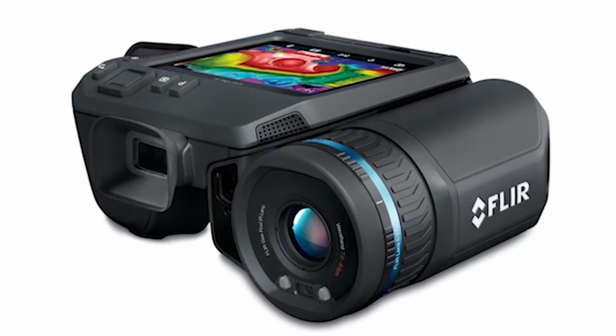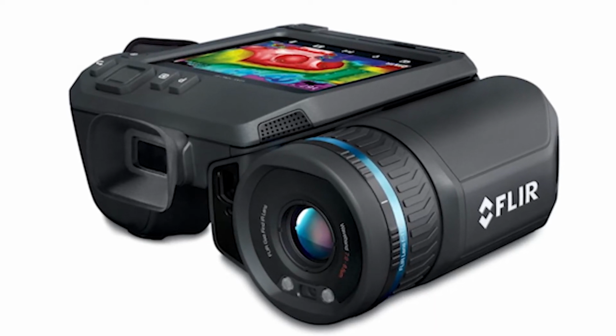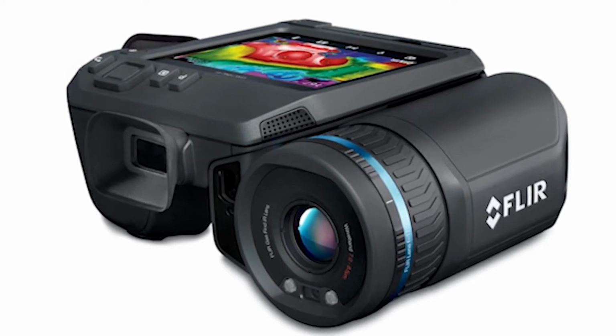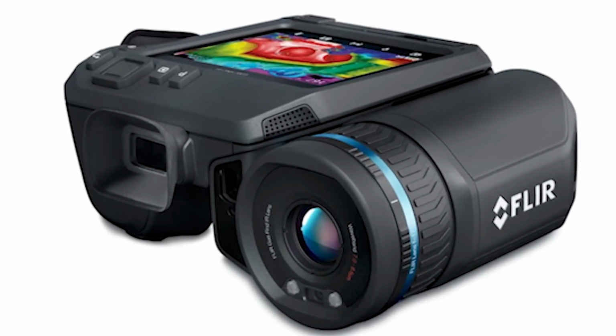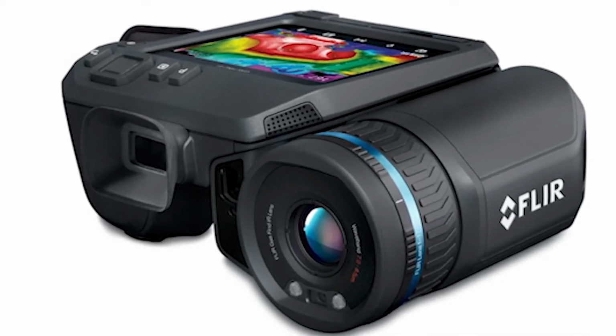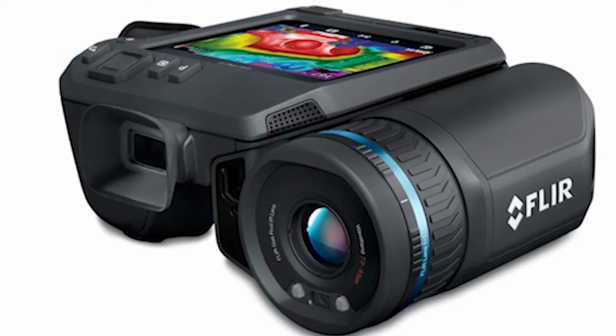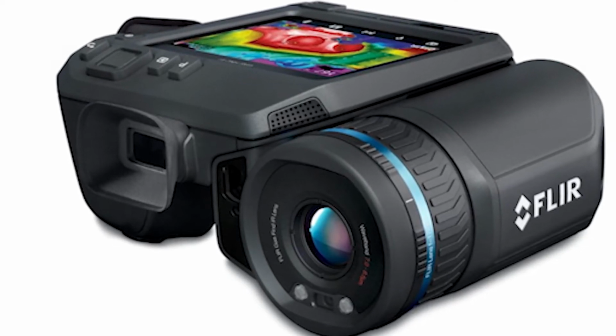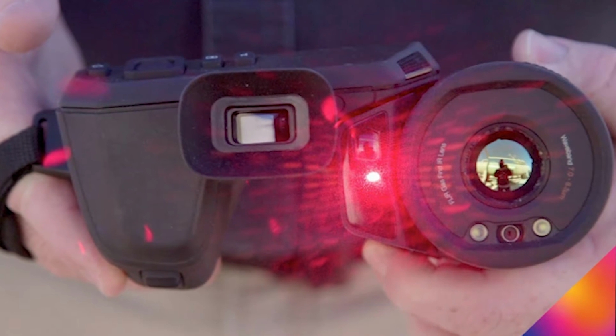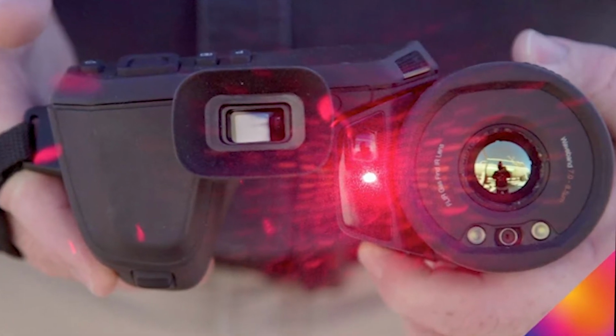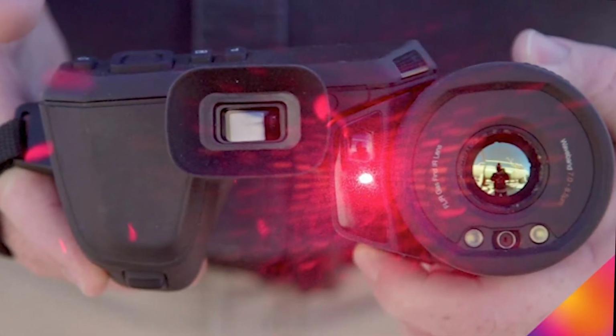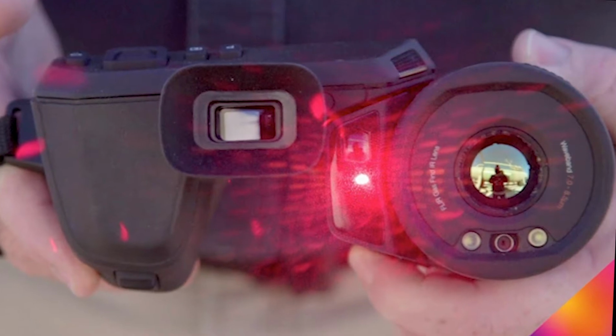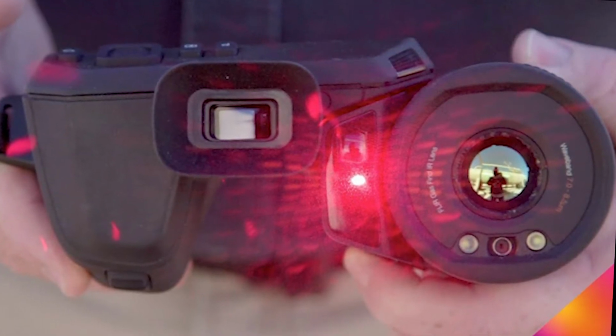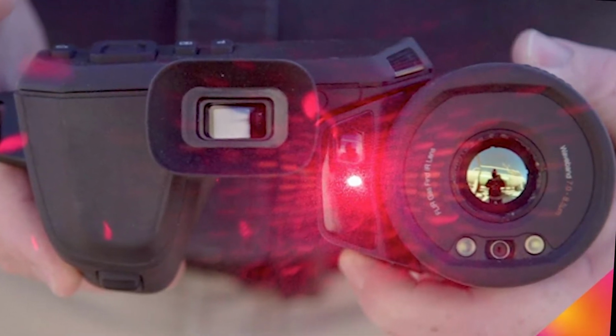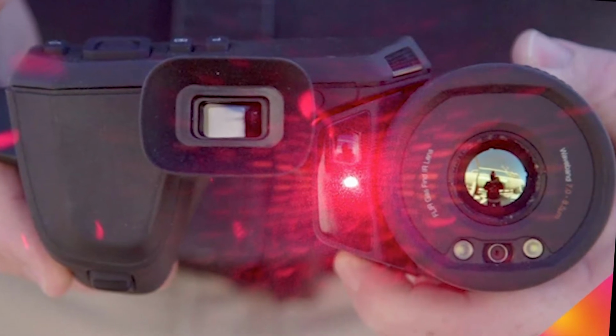The camera not only detects SF6 gas leaks and other gases, it also has forward-looking infrared imaging capabilities with all the bells and whistles, and it's able to capture full spectrum images with the integrated camera array and toggle between them. You can see a red laser which is illuminated beside the lens. This is the camera using its autofocus feature to determine the range of the subject and automatically focus, giving us the best possible image. This feature makes the camera virtually hands-free.